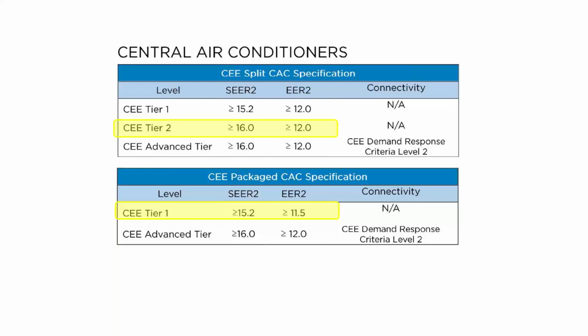There are 2 major ways that air conditioners and heat pumps get more efficient. One of those ways is to put in a variable speed compressor with a variable speed condenser fan. The other way is to put in a unit with a much bigger condenser coil surface area. Larger, wider, taller, bigger unit, more metal in it, more surface area. EER does not really get helped or improved by putting in variable speed stuff. EER efficiency really only comes from bigger surface area of the condenser for the most part.